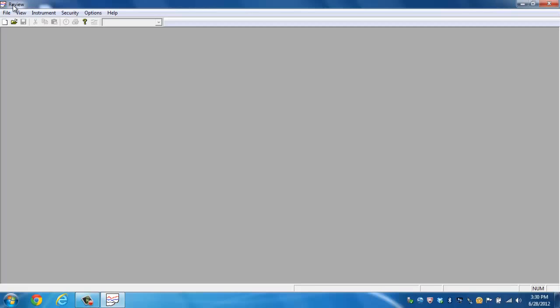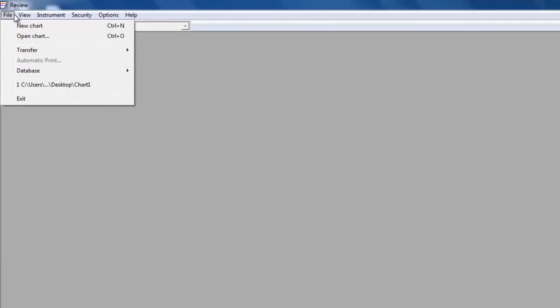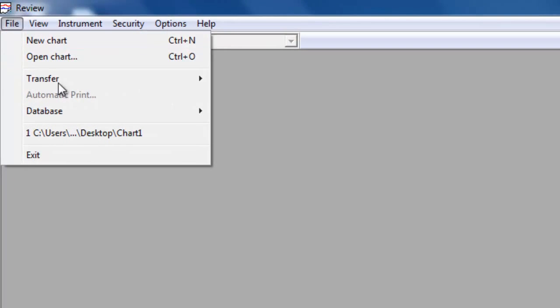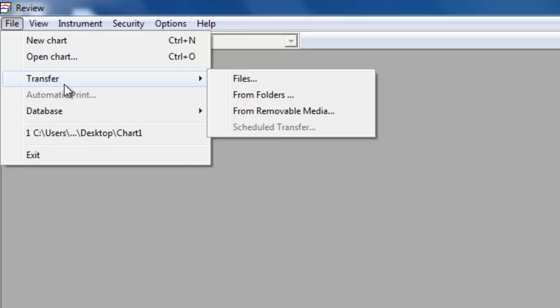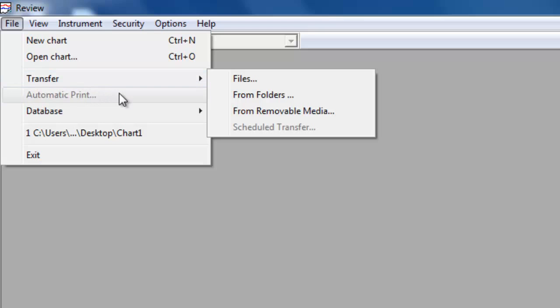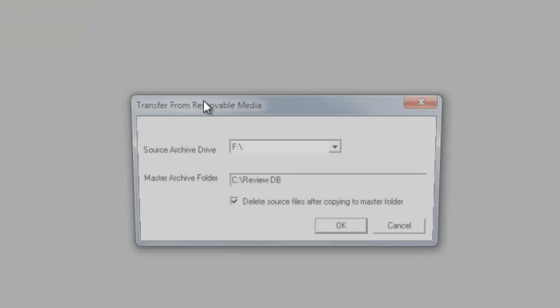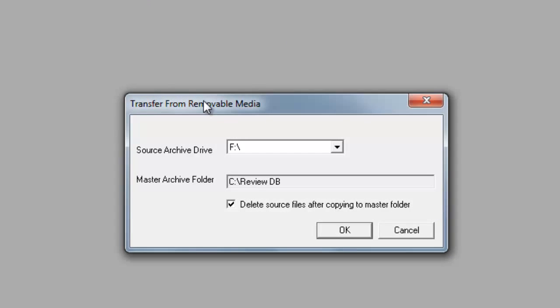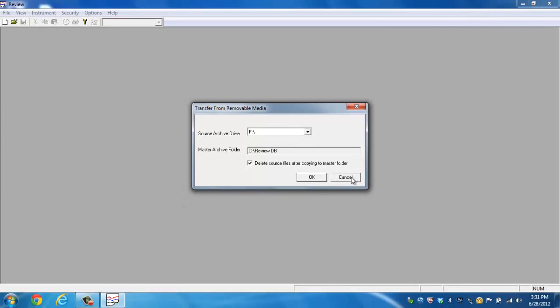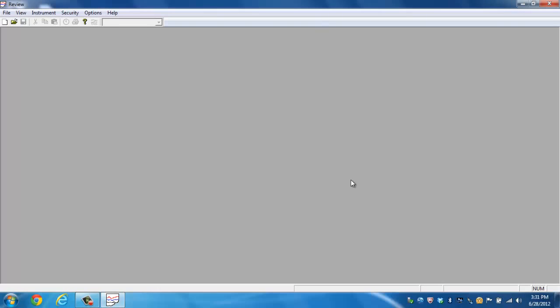The first thing that I would do upon opening up Review is determine how am I going to get the data from the Recorder into the database. In the event that your Recorder is not on network anywhere, you can do more of a manual method. The 6000 series and the NanoDeck both have USB ports on them. If you insert a USB stick up to 8GB in size, you can transfer the internal data over to that USB stick. By going to transfer from removable media, you can select that USB stick and transfer those files from the Recorder or NanoDeck. Hitting OK will bring over any file that it finds, and usually it won't take more than two to three minutes to complete.